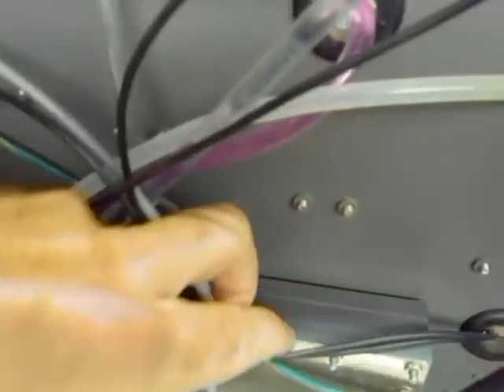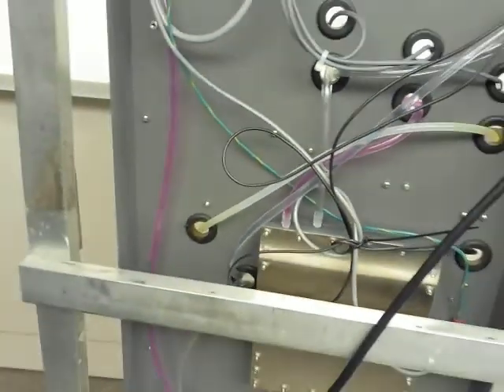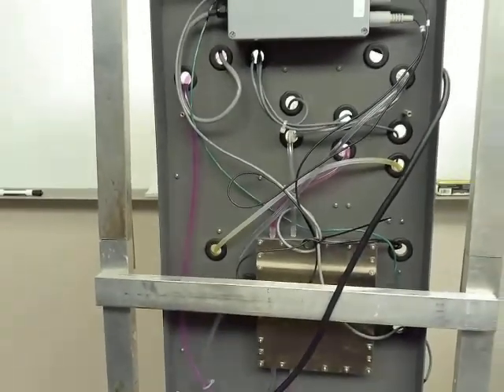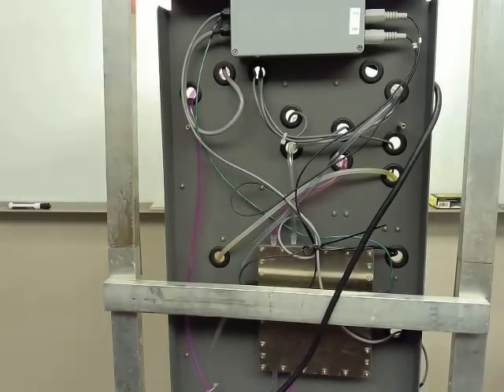So this heat exchanger has three plates. There's a middle plate, which has our sample running through it, and the two outside plates each have one of the calibration standards going through it. Each of those plates has a bunch of grooves cut through, with stainless steel plates in between them, which allows the samples to flow through and come in contact with those stainless steel plates and allow heat transfer to happen. Again, the heat exchanger is not actually doing any heating or cooling, it's just allowing the samples and the calibration standards to get to about the same temperature.